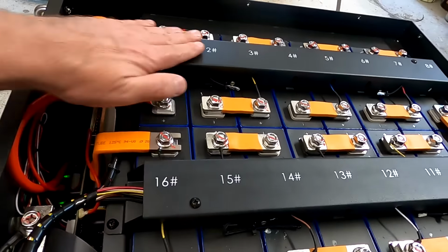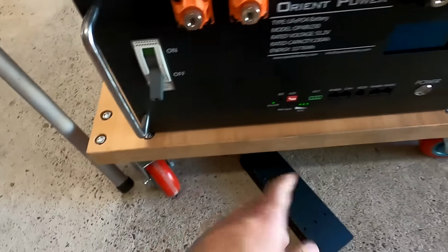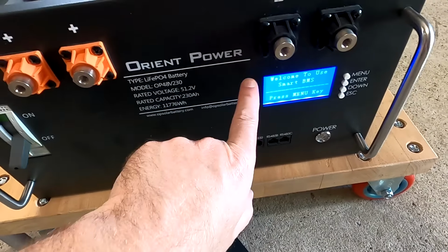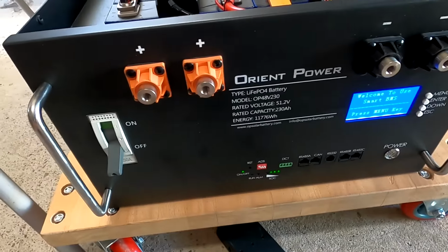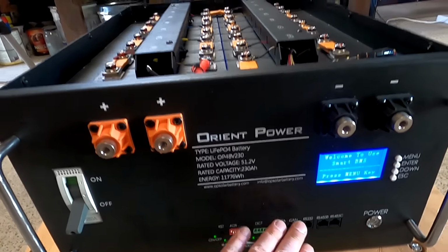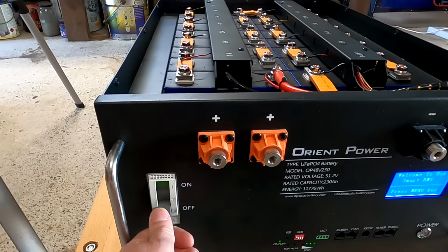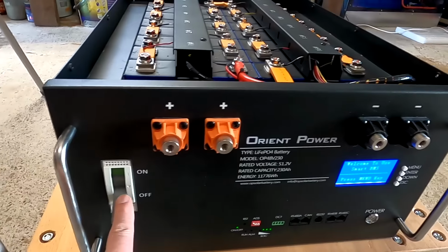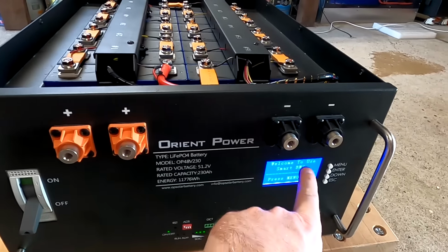The circuit breaker disconnects only the positive terminal. Even if you turn off the circuit breaker, the BMS is still connected to the battery, which I like very much. I always think the BMS should stay with the battery even if you isolate or disconnect it, because in case of a fault you have access to the BMS and can read all the data and check for any inconsistency or issues with the batteries.